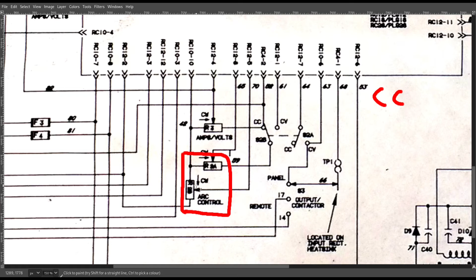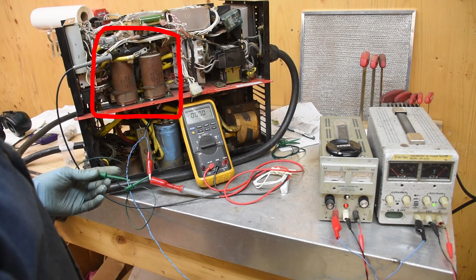Now what I'm doing here is testing the film capacitors, which are the two big ones there, one for each power section on the schematic, and I'm applying about 70 volts DC and measuring any leakage current, which would only tell me if it's really bad, defective, or if they're very different, but it doesn't guarantee that they're still good.